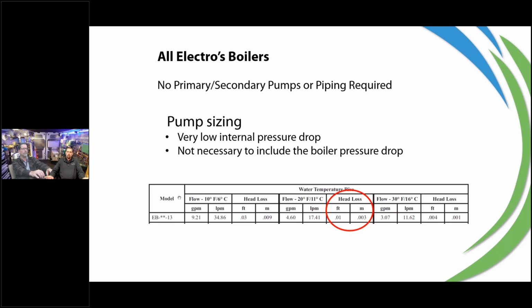When we're sizing out circulators, which we do a lot, the boiler really doesn't even come into play as far as flow rate or resistance - pressure drop through this thing is so low. As an example, flowing just about 5 GPM through this heat exchanger gives you a 0.01 pressure drop, so it doesn't hurt the circulator one bit. That makes it a little easier to size, and some of our boilers already have the circulators built in, as you'll see as we go forward.